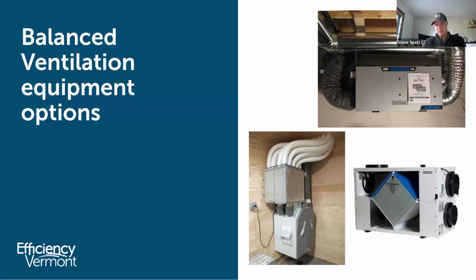Designing the system, you should be considering equipment that can meet that CFM requirement through the ASHRAE design that I'll show you more detail on in a moment. But the equipment should be sized to meet that minimum flow rate for the building within the middle to moderate range of capacity of the ERV or HRV. And what we should be looking at here is either multi-speed or, more ideally, variable speed equipment, so that you can dial the equipment in to be running at a low to middle speed to move the amount of ventilation air required to the house.